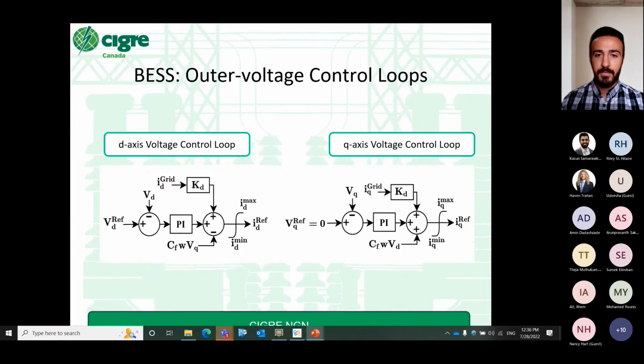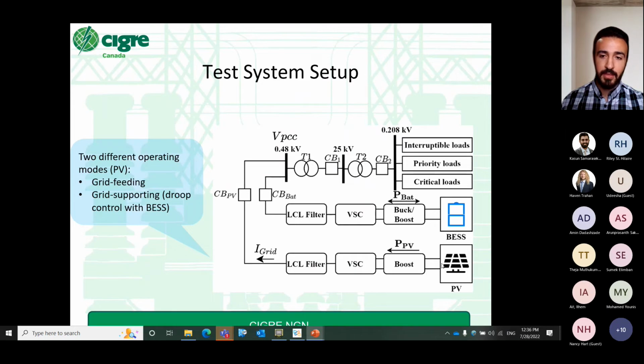So if you go to the test system setup, what I have in my thesis is a battery energy storage system and a PV and two diesel generators, which are interfaced with an RTAC, which has my power management system control. The way I did it is that we did not use any amplifiers. We exported the analog signals from the RTDS to the RTAC using GOOSE messages, and GOOSE messages to control the PV and the battery energy storage system. The signals that I need from my power management system are reference powers for the battery energy storage system and the PV, and grid forming, perhaps a control signal. It's not a part of this topic or this system setup.